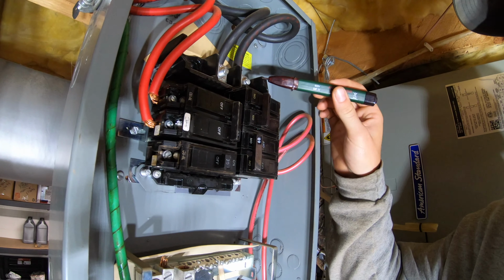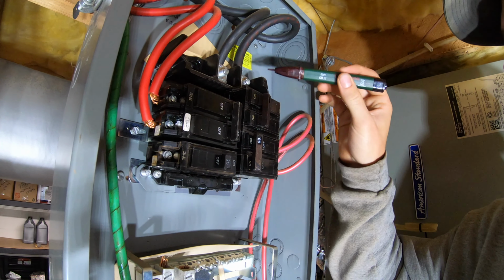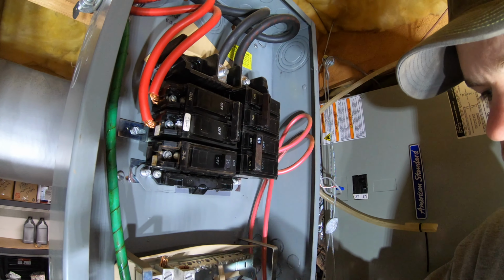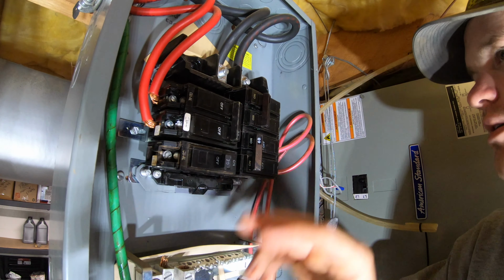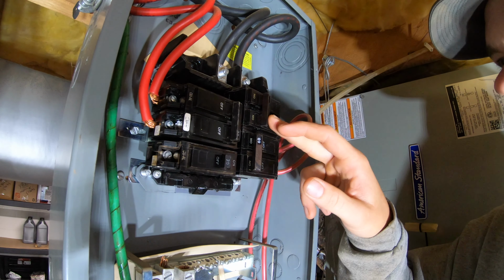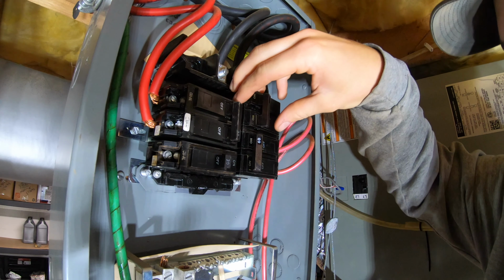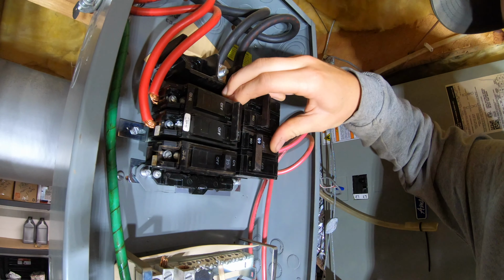Alright, let's check our power again. I'm going to remove this 60 amp here because it's not in service. I'm going to install a 30 amp which will run that compressor safely.